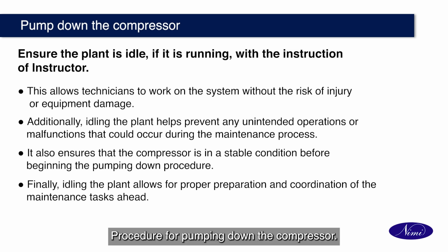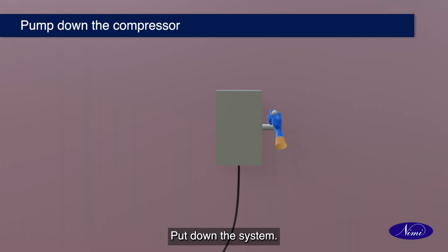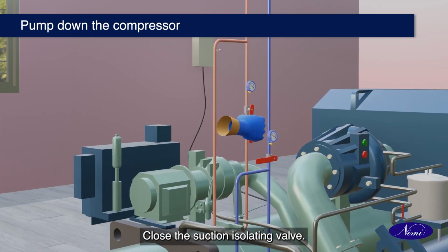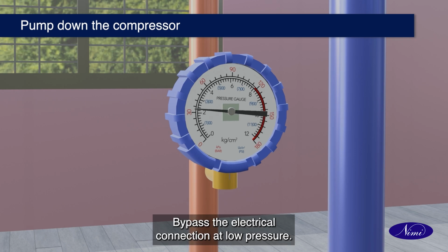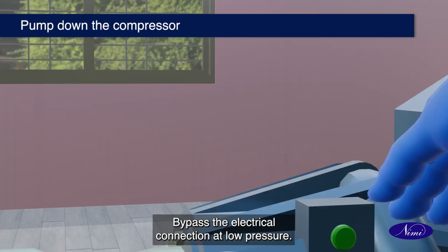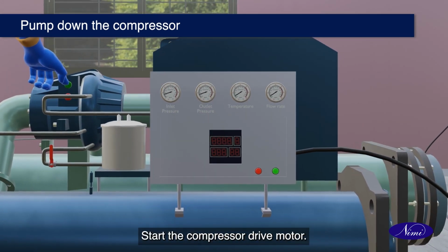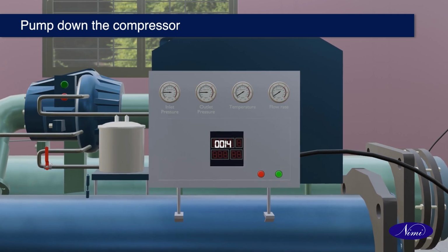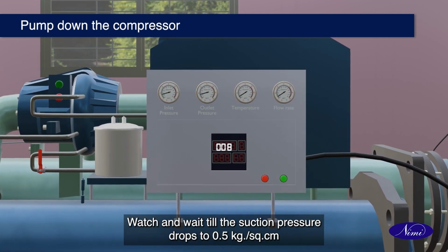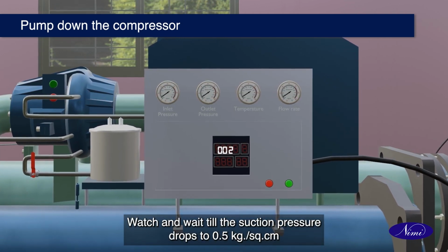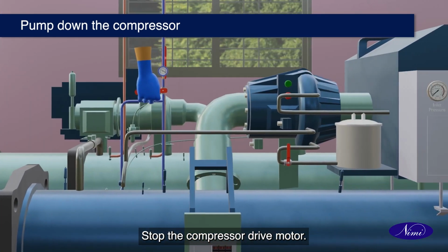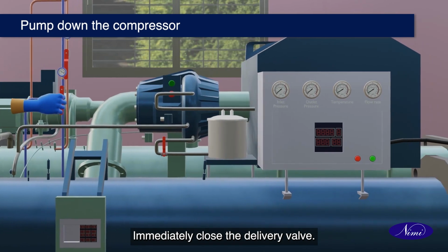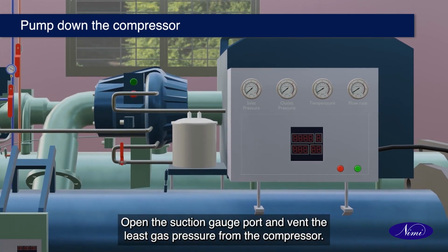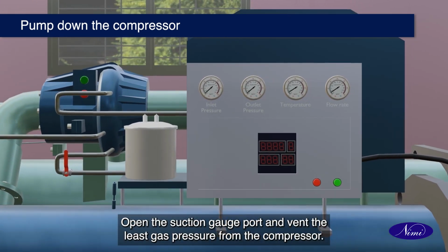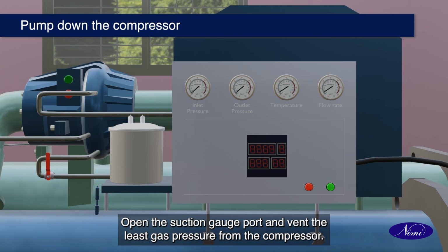Procedure for pumping down the compressor. Put off the system, close the suction isolating valve, bypass the electrical connection at the low pressure cutout switch, start the switch, and start the compressor drive motor. Watch and wait till the suction pressure drops to 0.5 kg per square centimeter. Stop the compressor drive motor. Immediately close the delivery valve. Open the suction gauge port and vent the residual gas pressure from the compressor.